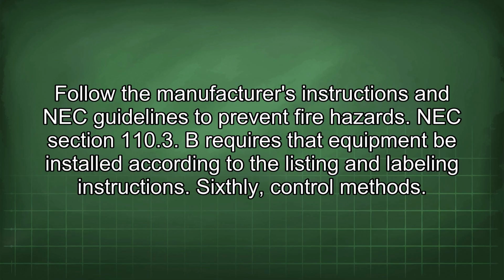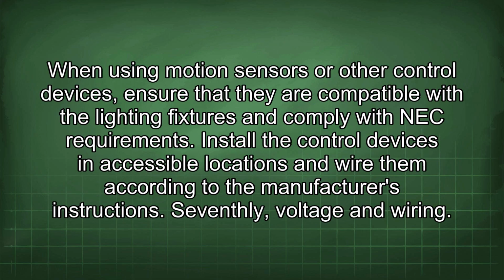Sixthly, control methods. When using motion sensors or other control devices, ensure that they are compatible with the lighting fixtures and comply with NEC requirements. Install the control devices in accessible locations and wire them according to the manufacturer's instructions.